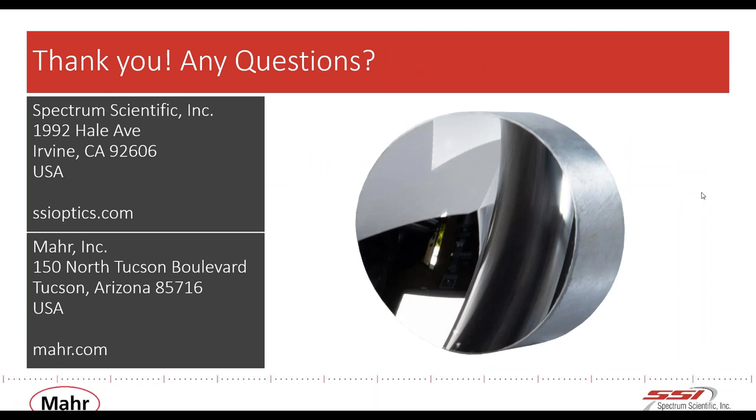The point is a great one — if you can get several measurements on one part, you feel much more confident. We don't always have the luxury of having multiple tools. Especially if it's beyond what an interferometer can measure, you've got contact or non-contact probes that need to be used. That tails back to the first question: how do you know how accurate your measurement is? What I've seen in the metrology world is the accuracies are quite good — around 10 nanometers, which is fantastic. At the Mahr booth at Photonics West, you'll see quite impressive specifications, and I've learned to trust them as long as the user is doing it right.